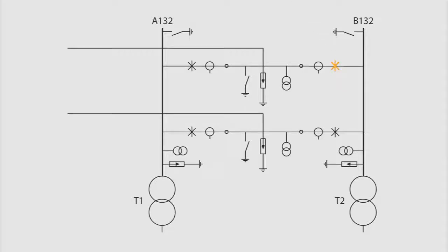Since there are no conventional disconnectors in the substation, the physical separation needed to enable maintenance of the disconnecting circuit breaker while the line is kept in service is achieved by the removal of the links between the line entrance and the disconnecting circuit breaker.